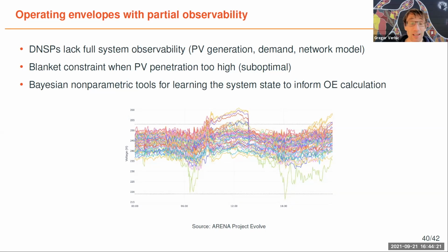The first project is operating envelopes with partial observability. I mentioned before that when you have large penetration of rooftop solar, it can happen in the middle of the day that voltages get too high. So this here is 255 volts, and the limit is 240 plus 6%, which I think is 254 volts as the upper limit. In the middle of the day, when people are away, nobody's using power, and PVs are generating and sending power to the grid, you get over-voltages. That's already an issue in many parts of the network, in particular Queensland and South Australia.